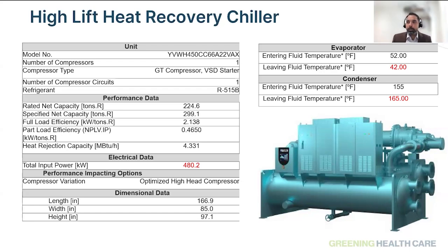One of the things I noticed, Robert, is that the part load efficiency of 0.46 kilowatts per ton is getting close to a centrifugal chiller just producing chilled water. Those are even slightly better in those cases. But what I noticed in the past with the heat recovery chillers was that if you used them only for cooling purposes, they're not as efficient as a centrifugal chiller. However, it seems that with recent changes we're getting close to that. These machines are getting more and more efficient. It all comes down to the individual project.